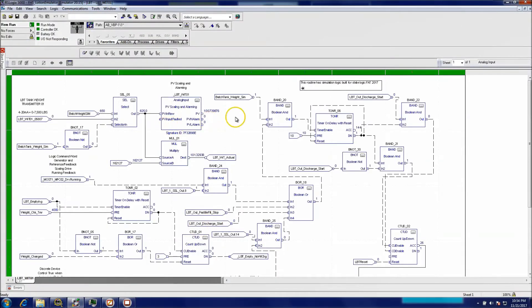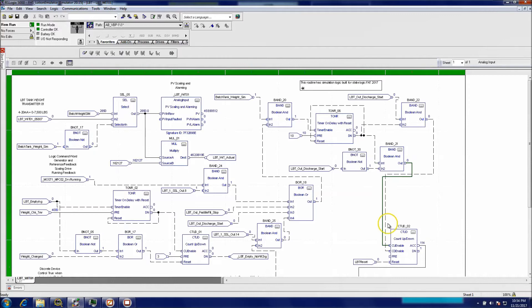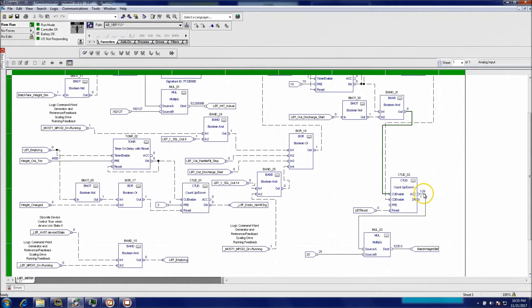Looking at the logic, what's happening is it's counting — it's saying basically that this is able to have a one and go through to the next. All of this is function block. It's good to the point where the timer can time out, and every time the timer times out it's going to reset via this bracket right here. As it goes through, when it gets done and this is not running, it's going to come down and index a one down to the counter, so the counter is basically counting up and multiplying by 25.